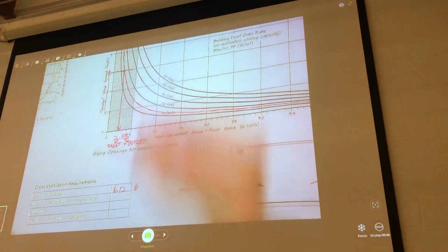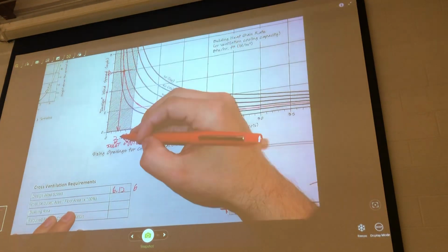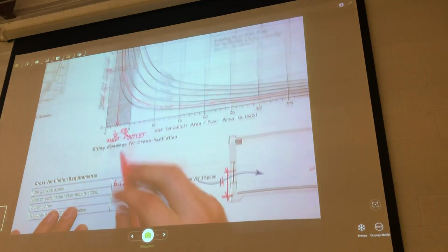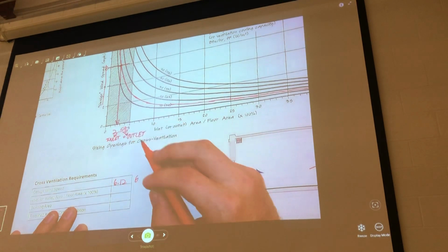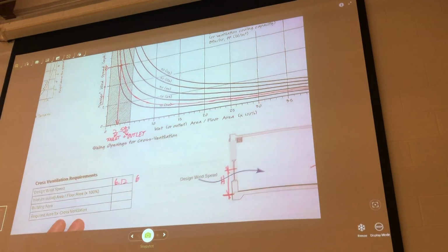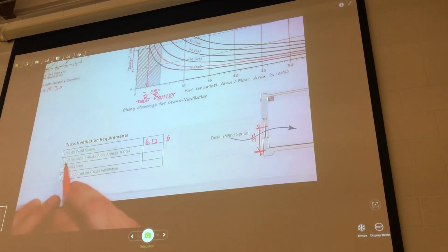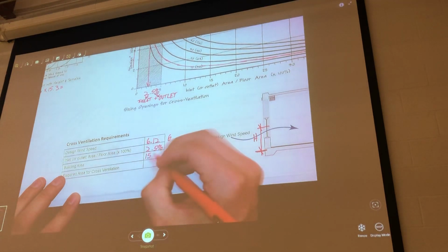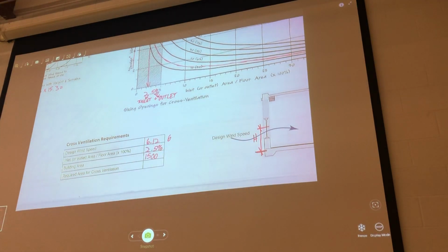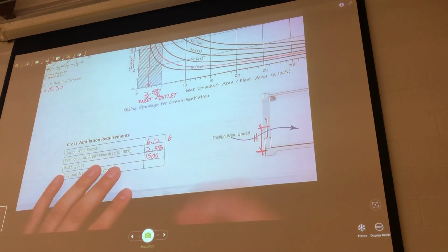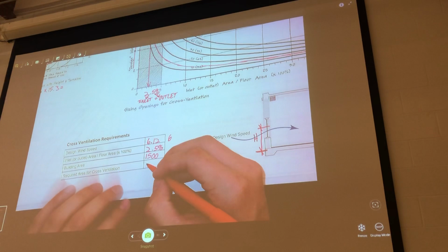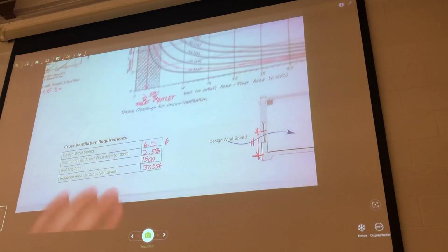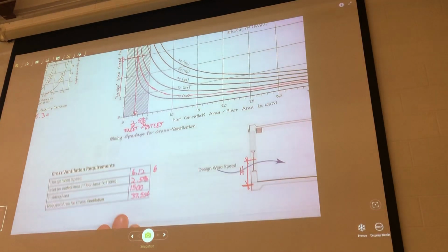So yes, even though when we actually draw this out, we're less than this 5% code minimum operable, we're actually providing 2.5 for inlet and our 2.5 for outlet. So that means 2.5 for our inlet, 2.5%. Our building area still has not changed. Which means we're going to need 37.5 square feet of operable inlet and operable outlet.